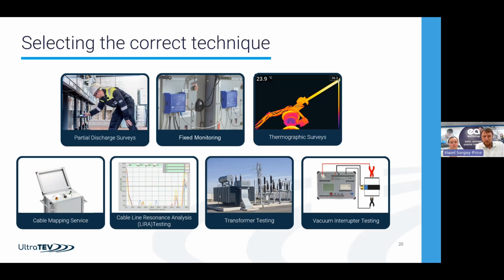So quite often it's taken as a follow-up service once you initially identify PD in a live situation. Before you go and joint the cable, you'd use that technique to locate it or build on the location we'd already given. There are also fingerprinting type technologies, which are often used on longer cables. It allows you to look at how the frequency response of the cable has changed over time.